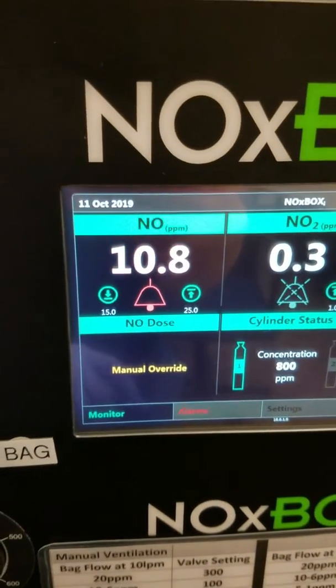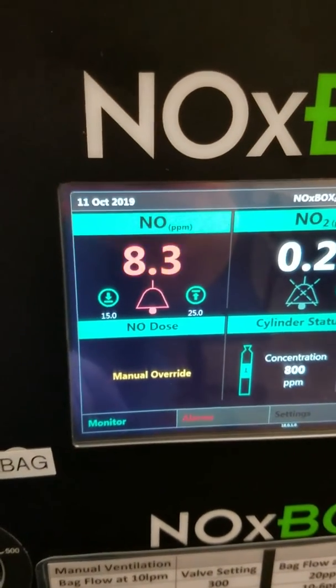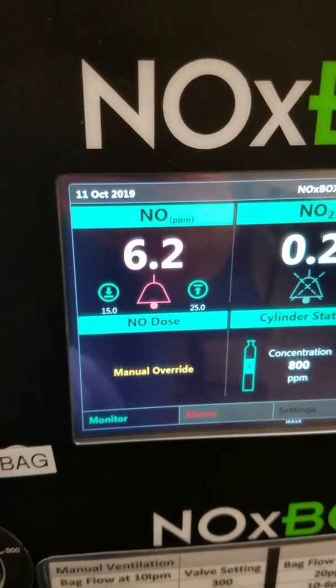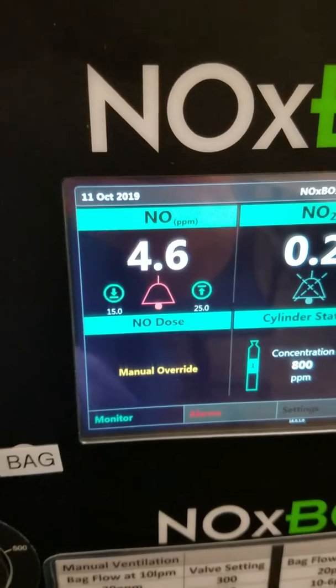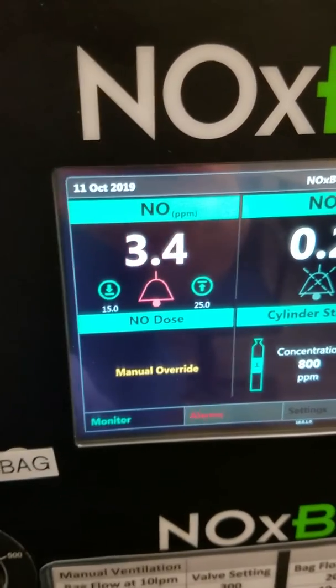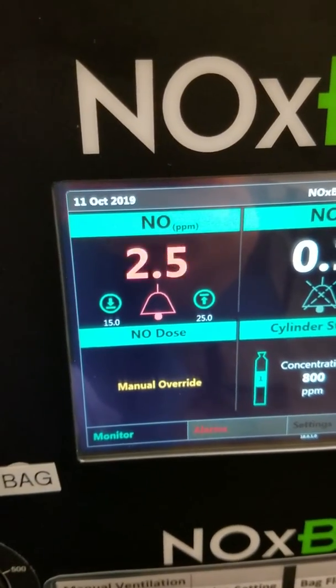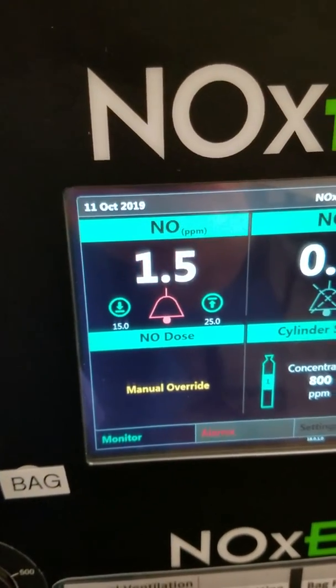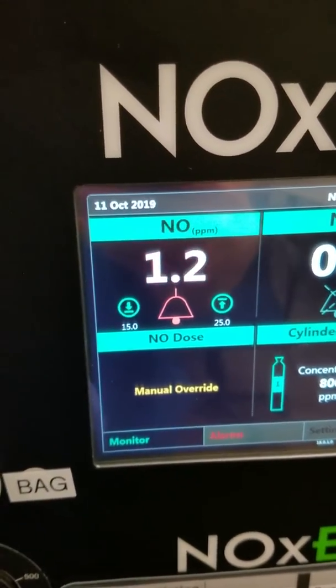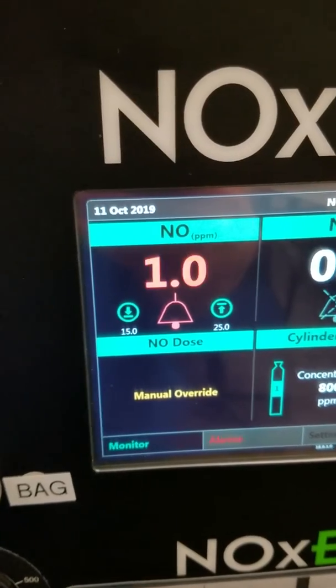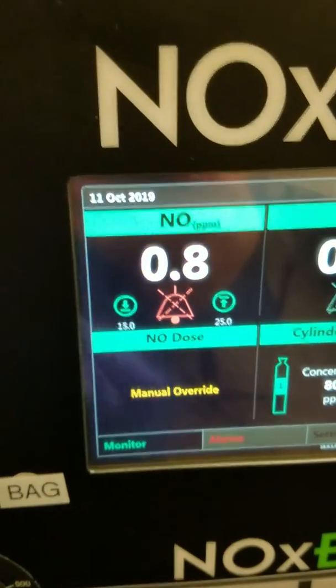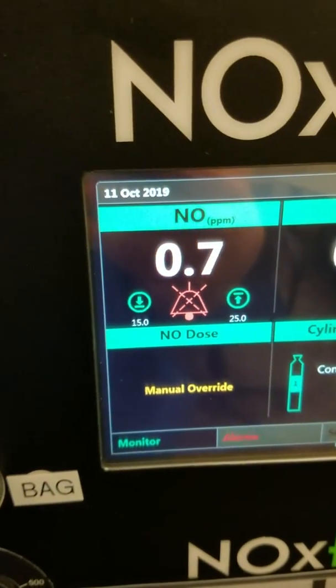The next alarm that's going to go off is going to be your NO delivered. As my sample line is still in my ventilator circuit, it's now going to start going down to zero. You can just hit the bell in the middle and it will silence that alarm.